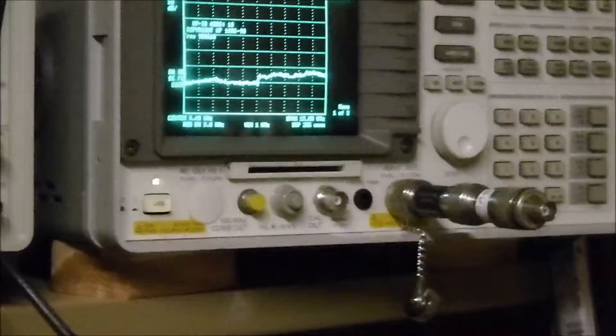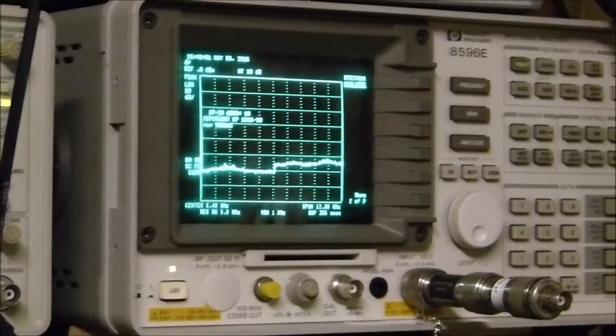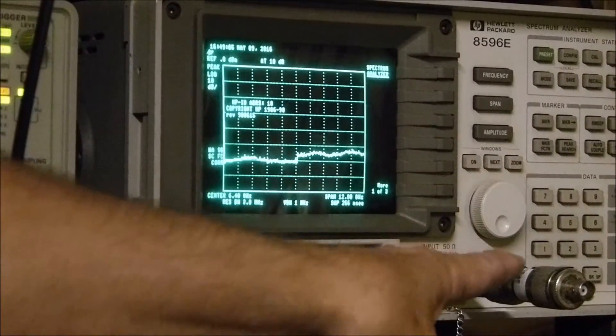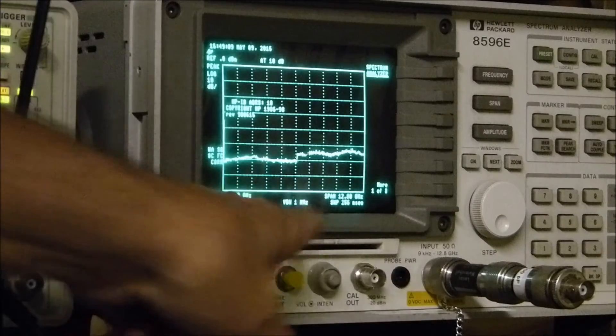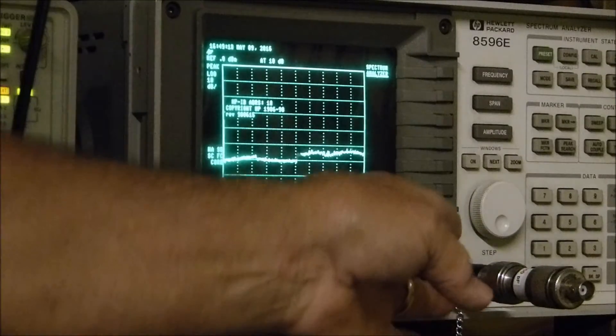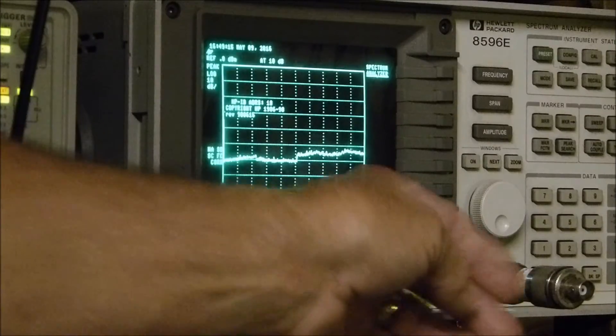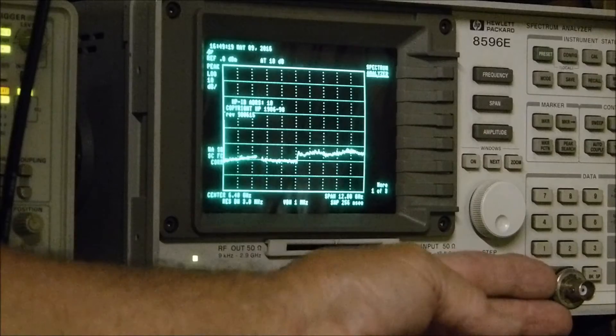On a spectrum analyzer like this beauty up here, you have to be extremely careful because the maximum DC is zero or you'll destroy the front end. That's why I use a capacitor coupler. The absolute maximum input is one watt, so I use a 20 dB attenuator.